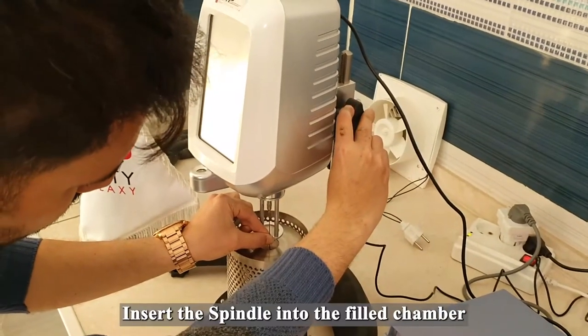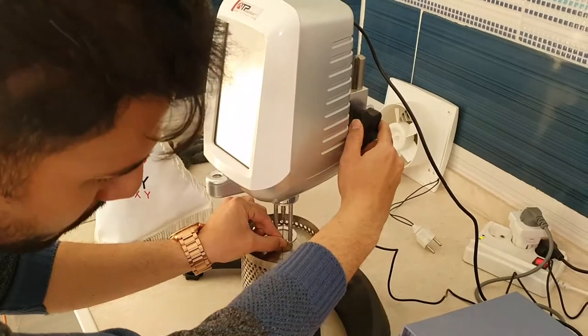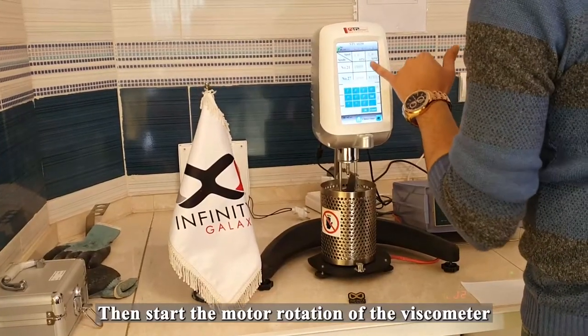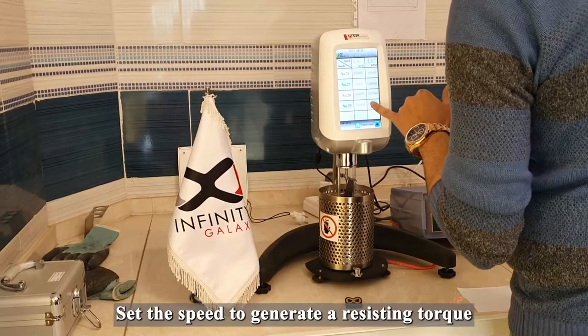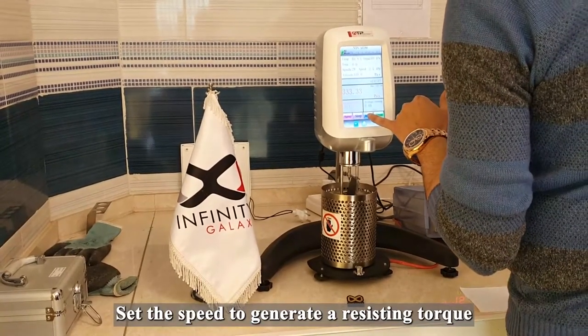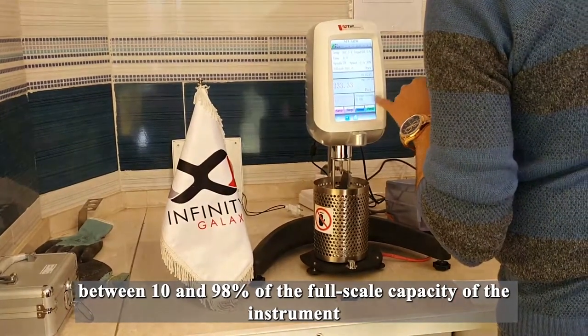Insert the spindle into the filled chamber and couple it to the viscometer. Then, start the motor rotation of the viscometer. Set the speed to generate a resisting torque between 10 and 98 percent of the full-scale capacity of the instrument.